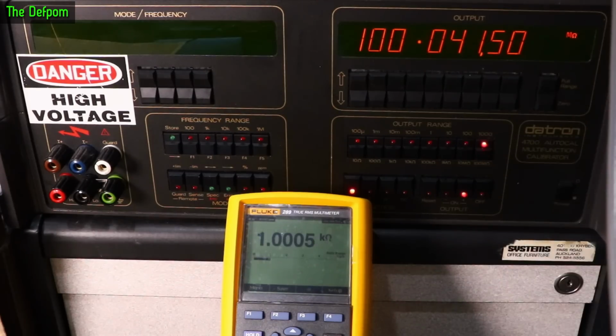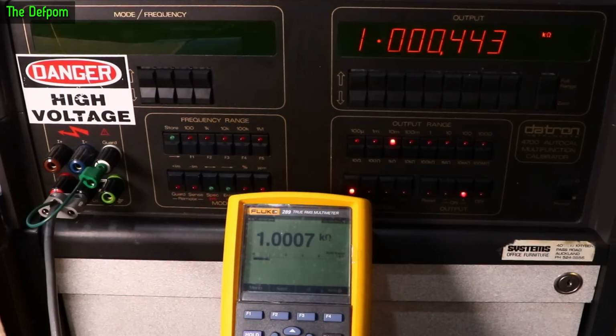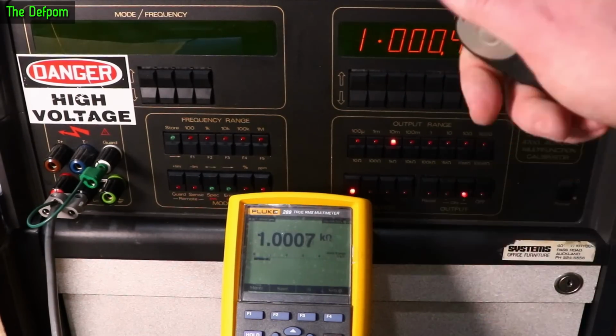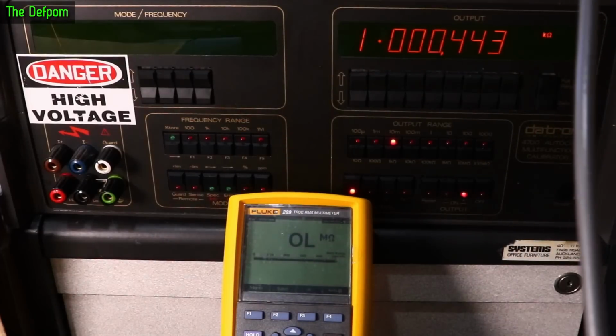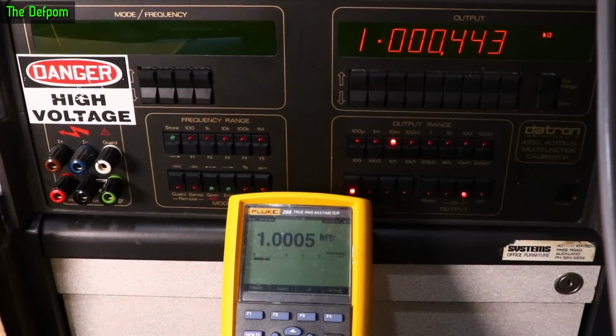It's 3 counts high. Let me recheck this one. Yeah, 3 counts high. That agrees. No worries at all. Just doing a second verification, just in case I've got a bad relay, because it can happen. I've had to repair relays on this Fluke calibrator before.